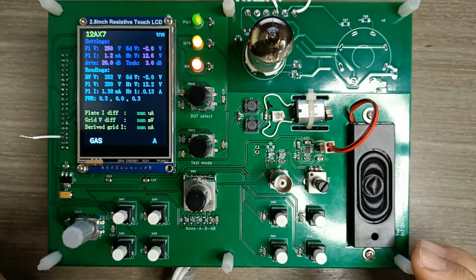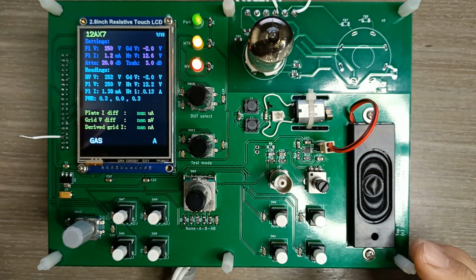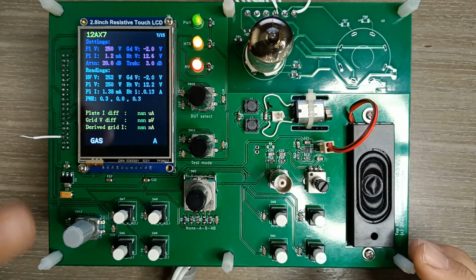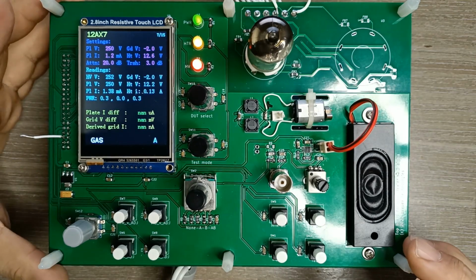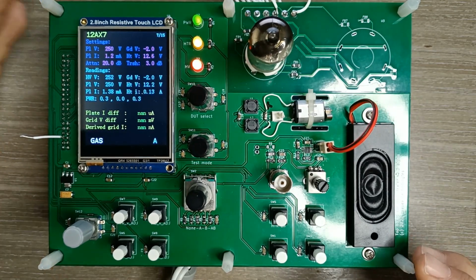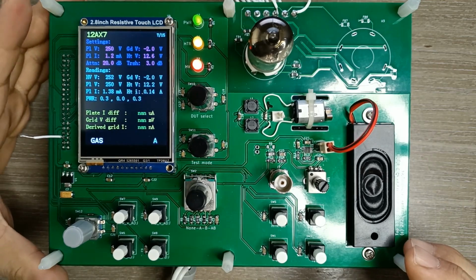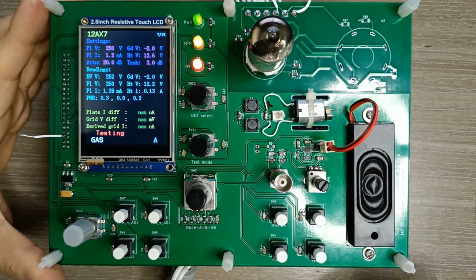Like I said, you can set the quiescent point at any value you want, and you can check the grid current under that operating point. On the TV7, it only tests the grid current at a fixed operating point. So now we can do a test.